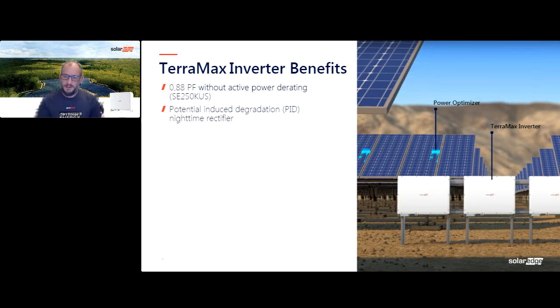A lot of times, with other string inverters, this requires an external box to be placed on that DC bus. So if you have a string inverter, especially a multiple-input string inverter, you now have to put this device on every single input, because it will affect pretty much every string out there. Because we have long strings, we have a single input DC bus into our inverter, so you only need that one inverter to have the PID nighttime rectifier. And so that's built in and included with our inverters.